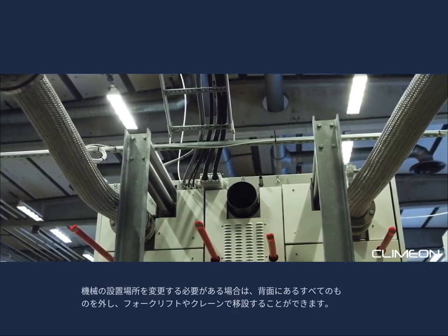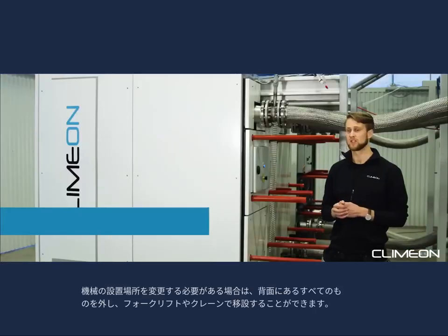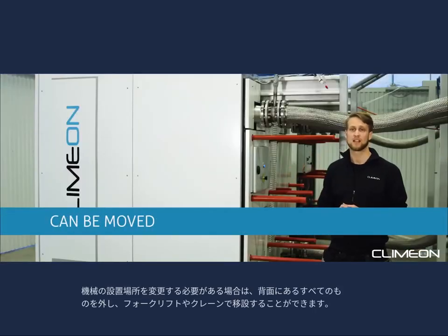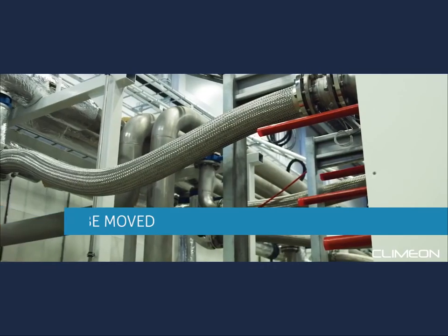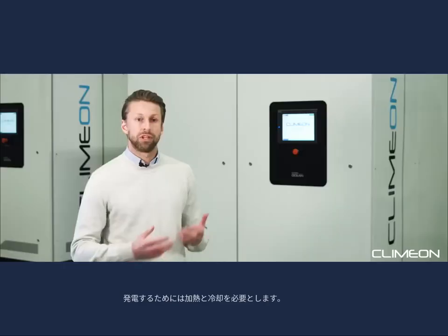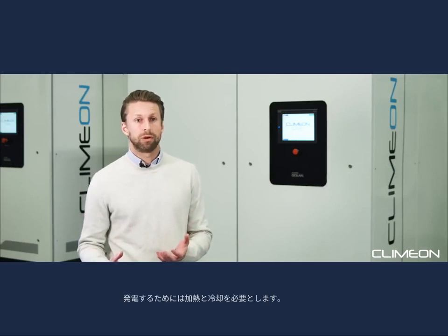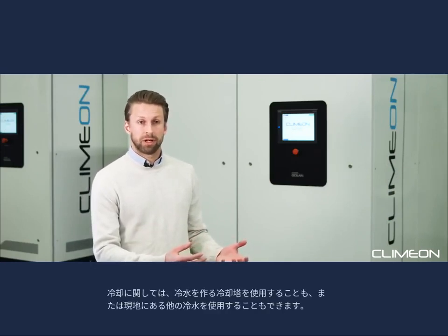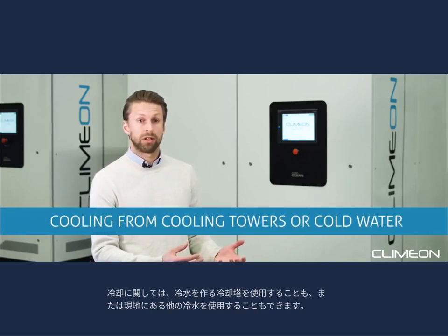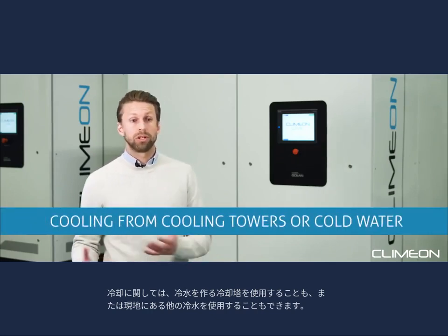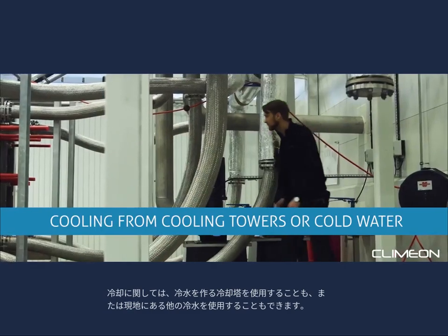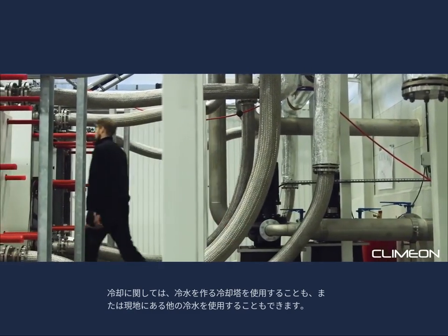If you need to change the site of the machine, that is possible. You can just disconnect everything in the back and simply lift it with a forklift. The machine requires heating and cooling in order to perform. Regarding cooling, you can choose either having cooling towers, creating the cold water that you need, or you can use other kind of cold water that might be available at the site.